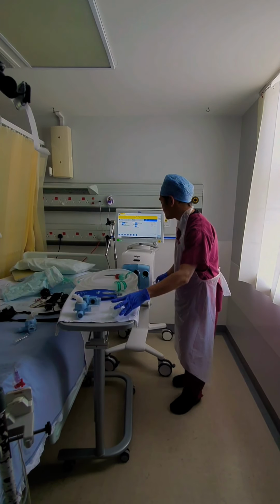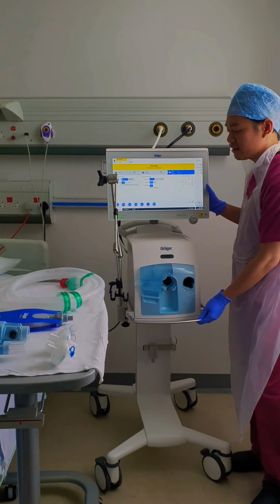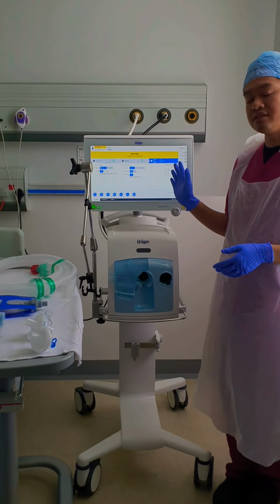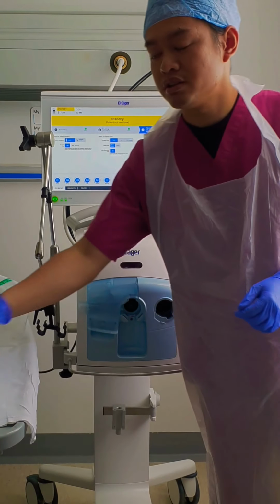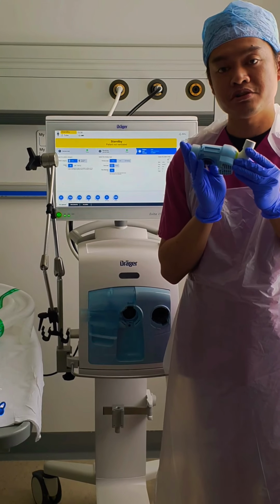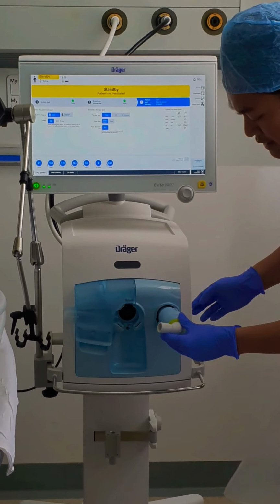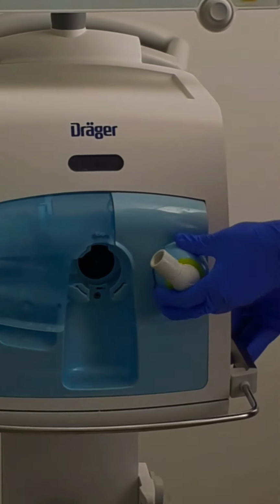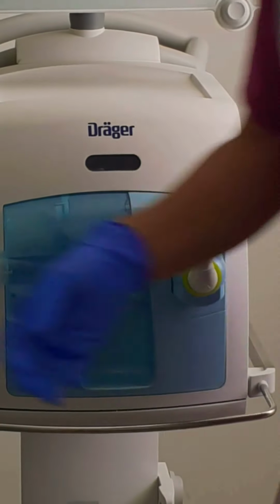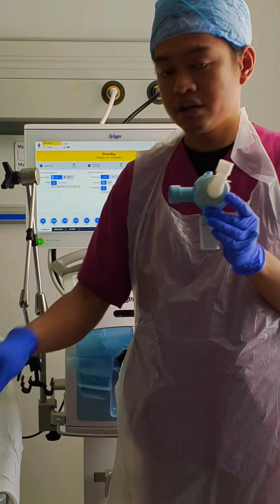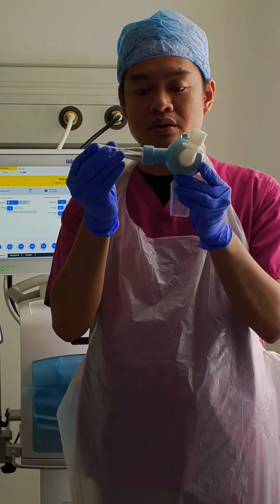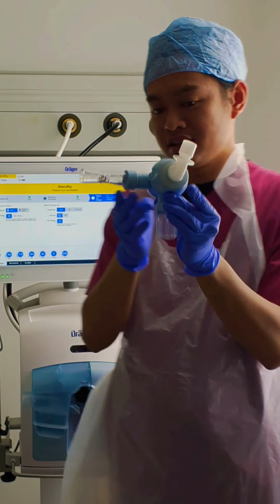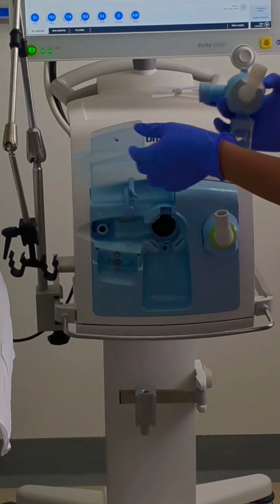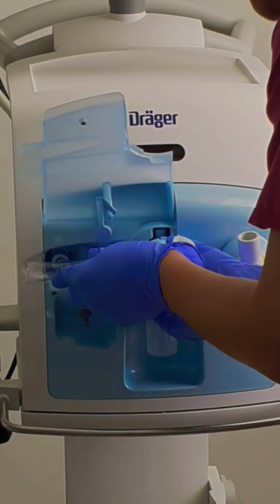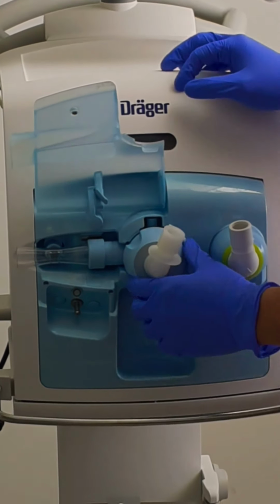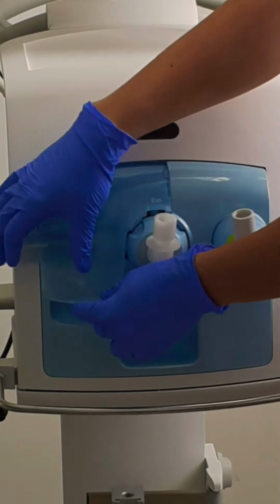Now I'm going to show you how to actually set the ventilator up. Again, this is the Evita V800 ventilator, and I have already turned it on. First I'm going to show you how to put the inspiratory port in. It goes in at this angle, and then you just twist it to lock it in place. Next is your expiratory valve. What I do is connect the flow sensor to the expiratory valve and put this on the machine as a unit. Lift up the cover, push this in as a unit, twist it to your right to lock it in place, and then put the cover down.